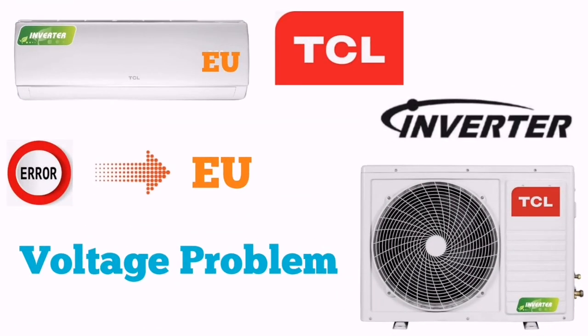When you see error EU, it means outdoor voltage problem. First of all, check the input power supply. Check if the input power supply is correct, 220 to 230 volt or not. And if your power supply is correct, then you have to check the communication wire between the outdoor power source board and the intelligent power module board.